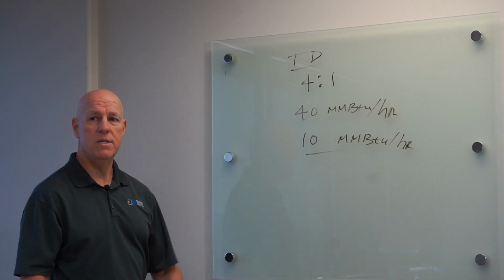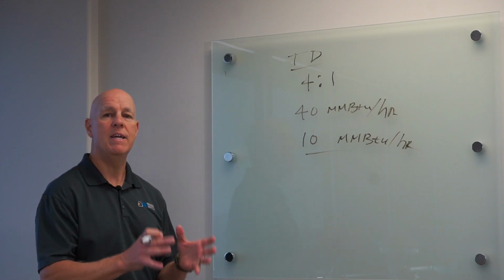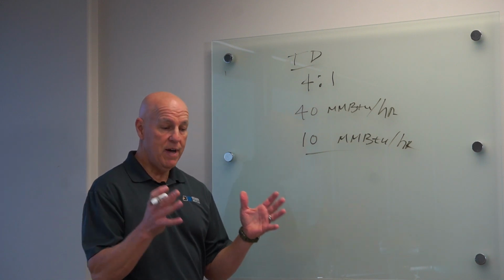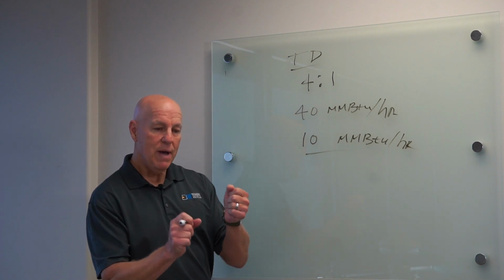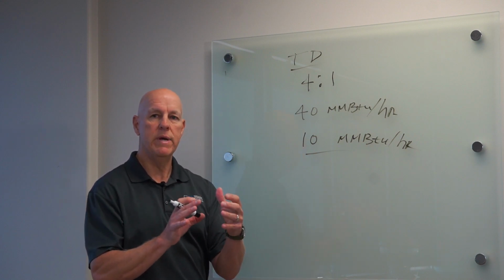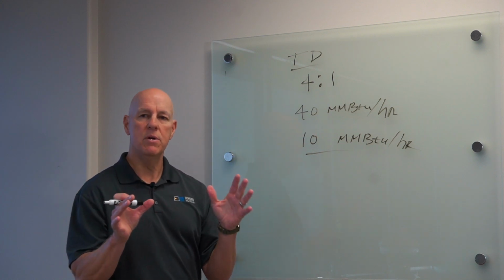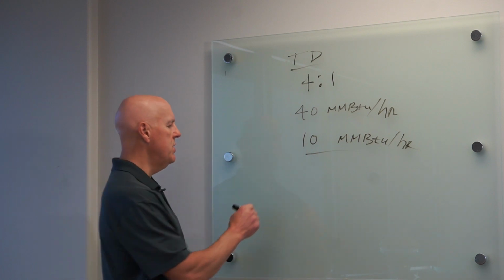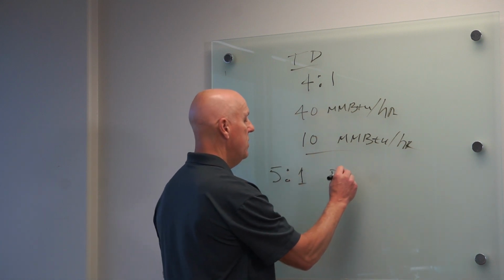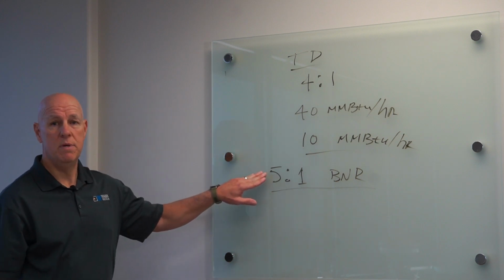There is. So let's think about two things. One, let's talk about a burner. The burner is actually providing the heat. It's like the engine of the car. If I have a flame and I start backing the fuel gas down on that flame, the flame gets smaller and smaller. At some point, that burner won't be stable. It just simply blows out. Typically, a reasonable burner turn down is in the range of 5 to 1. If you go significantly lower, you may have a stability problem with the burner.